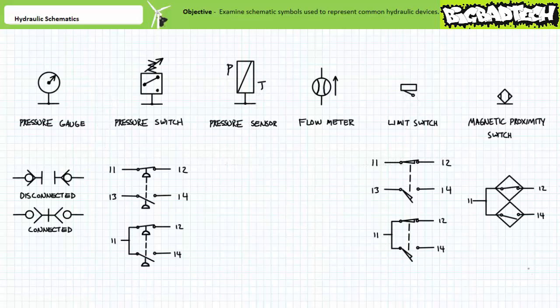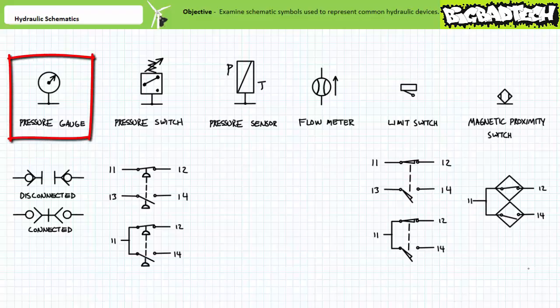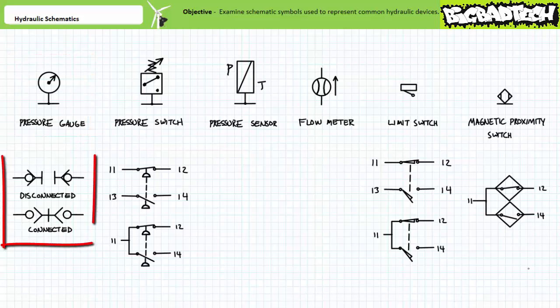Given flow rate, pressure, and direction in a hydraulic system must be controlled to perform some task with the required speed, strength, and precision, it helps if these quantities are measured using common instrumentation, switches, and sensors. The schematic symbol for a pressure gauge or manometer is a needle in a dial. If a system includes quick disconnect inspection ports for portable instruments, they're often indicated as check valves. When disconnected, the check valves are closed. When connected, the balls are pushed off their seats and connection allows flow.